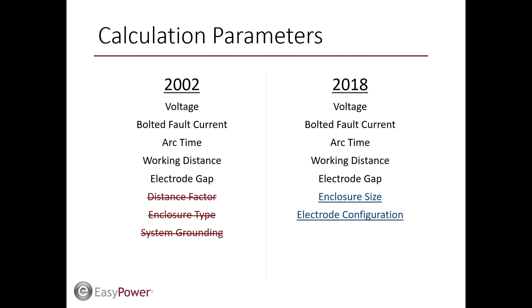Calculation parameters: these represent the system characteristics used to calculate arc flash. Voltage, bolted fault current, arc time, working distance, and electrode gap all remain from the original standard. Distance factor from the original standard has been replaced with enclosure size, with variables of height, width, and depth. Enclosure type from the original standard has been replaced with electrode configuration, which further expands the original parameter to also include electrode orientation. System grounding from the 2002 version is no longer considered.